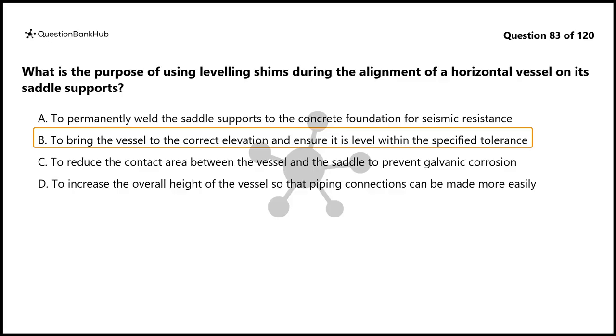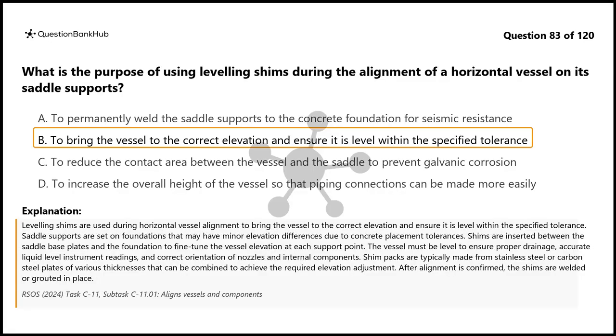The correct answer is B. Leveling shims are used during horizontal vessel alignment to bring the vessel to the correct elevation and ensure it is level within the specified tolerance. Saddle supports are set on foundations that may have minor elevation differences due to concrete placement tolerances. Shims are inserted between the saddle base plates and the foundation to fine-tune the vessel elevation at each support point.